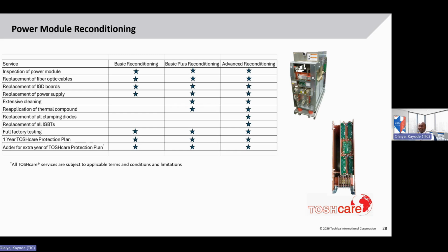The basic plus adds extensive cleaning. So the steps I mentioned in the previous slide were for an advanced, which is where the module will be disassembled and cleaned. That is also done with the basic plus reconditioning. In that case, we do not replace the power devices. We just reapply thermal compounds to make sure that there's proper heat transfer between the power devices and the heatsink. So that's the difference between the basic and the basic plus. This is extensive cleaning and, highlight that here, extensive cleaning and reapplying the thermal compound.